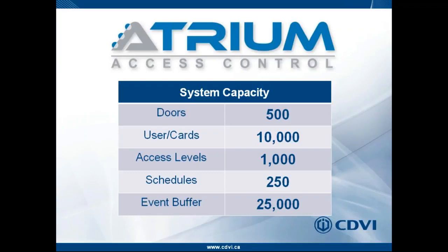However, when you do connect to the system with the software, one of the advantages of the software, the advanced features, if I will, when you connect to the Atrium system, the event buffer will be copied onto the computer's hard drive of that software. So as soon as I connect with the Atrium software, all the events that are located in the A22 event buffers will be downloaded onto the computer's hard drive and stored there into an SQL database.